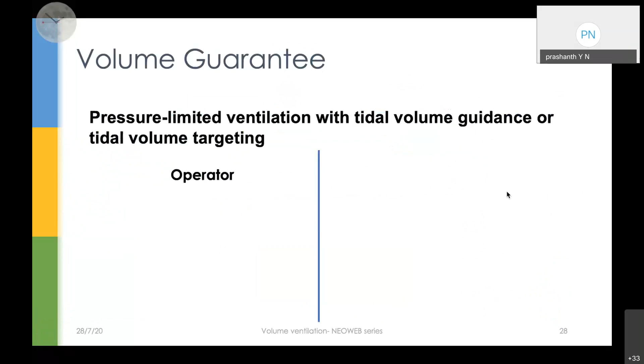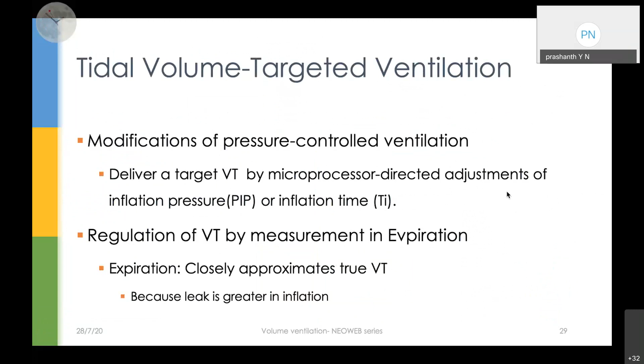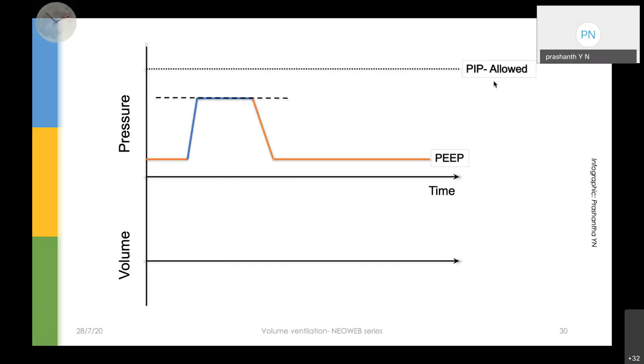So what our volume guarantee does is the same. It looks at the volume which is coming out of the lung to decide how much pressure it has to give to push air into the circuit in the next breath. This is just an infographic for your understanding. We put in the peak inspiratory pressure allowed. That means I'm telling the ventilator, this is the maximum you can go up to. After that, you can't go beyond this pressure.